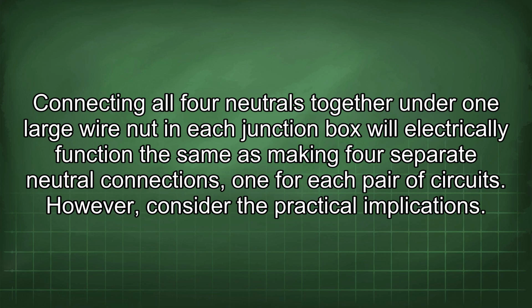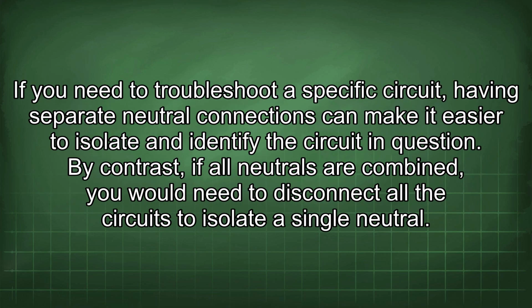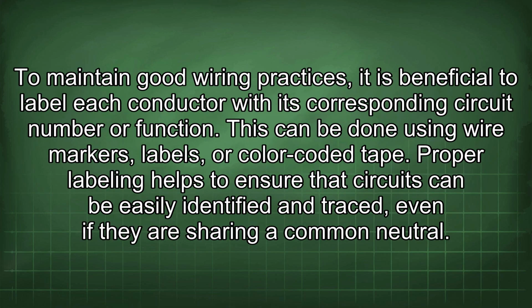However, consider the practical implications. If you need to troubleshoot a specific circuit, having separate neutral connections can make it easier to isolate and identify the circuit in question. By contrast, if all neutrals are combined, you would need to disconnect all the circuits to isolate a single neutral. To maintain good wiring practices, it is beneficial to label each conductor with its corresponding circuit number or function. This can be done using wire markers, labels, or color-coded tape.